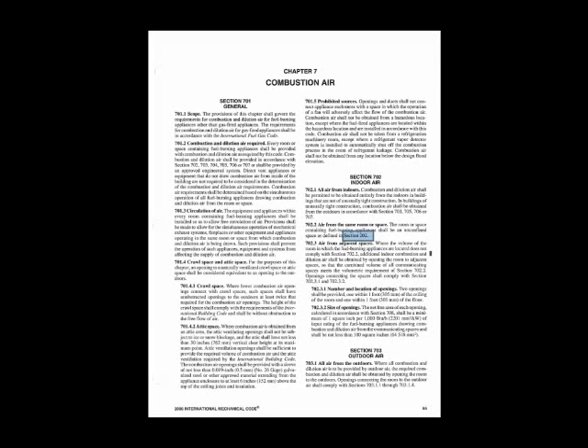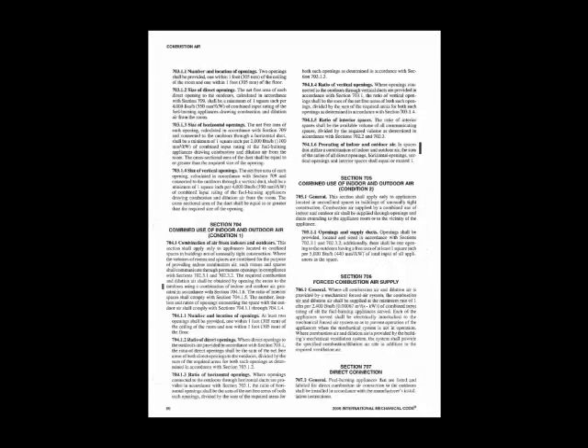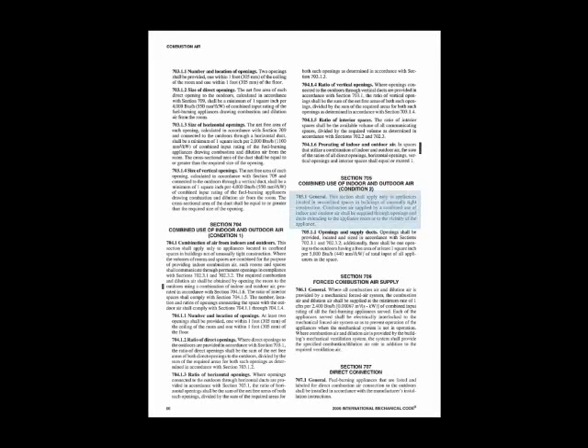Section 703 talks about the use of outdoor air as combustion air. 704 talks about the combined use of indoor and outdoor air for a certain condition. It gives you the size of the openings, the ratio of openings for both vertical and horizontal. They make a difference because hot air rises. Sometimes horizontal has wind direction, has indoor and outdoor spaces. 705 gives you the second condition, combined use of indoor and outdoor air for combustion. 705 specifically says this section shall apply only to the appliances located in unconfined spaces in buildings of unusually tight construction. In other words, a lot of insulation, very energy efficient.